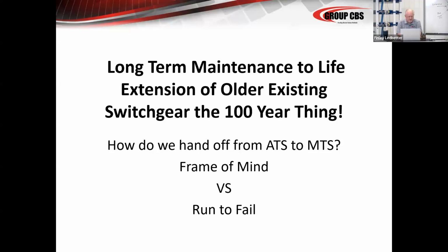Yeah. What I'm saying there is quite often when a breaker is inserted into a piece of metal-clad switchgear, the equipment's very heavy, and there's a lot of energy produced in racking the equipment onto the stabs and off. Then when the breakers open and close, there's a lot of energy exerted. They should not cut filings. By the time you get it, they've already been opened at the factory 30 or 40 times. They've been inserted 30 or 40 times. So in the bottom of the switchgear, underneath the racking device, underneath the charging motor, there should not be a pile of metal filings when the gear is brand new.